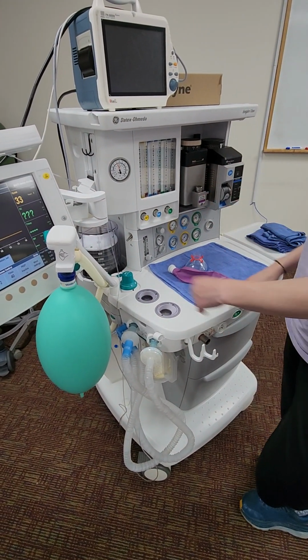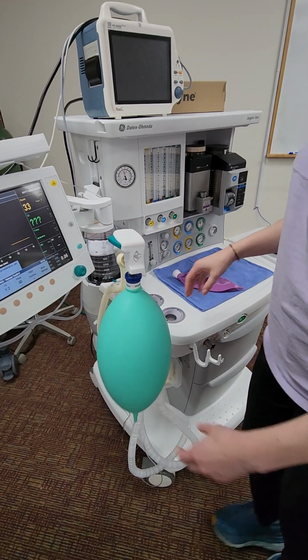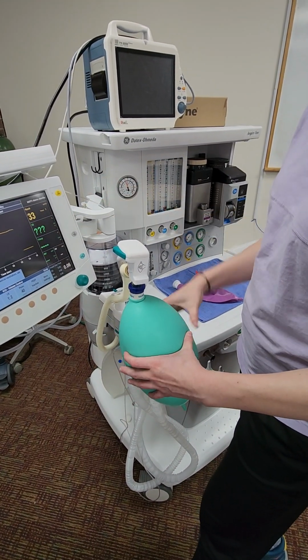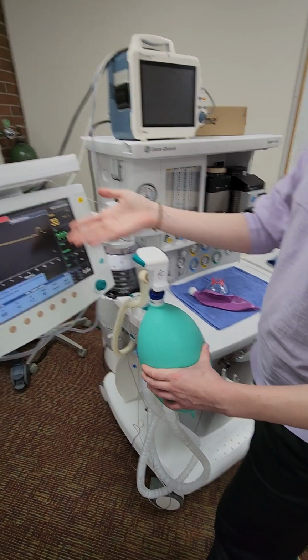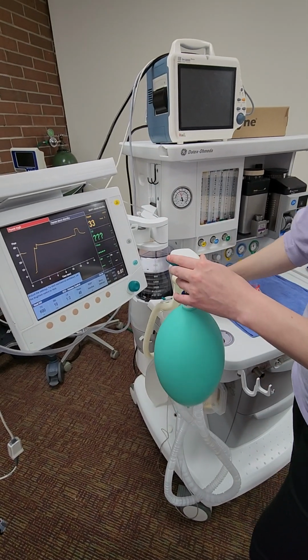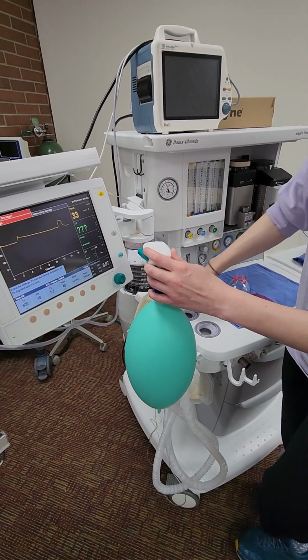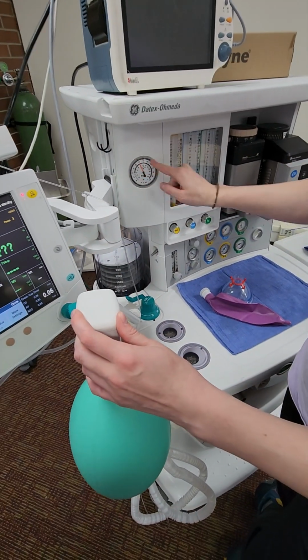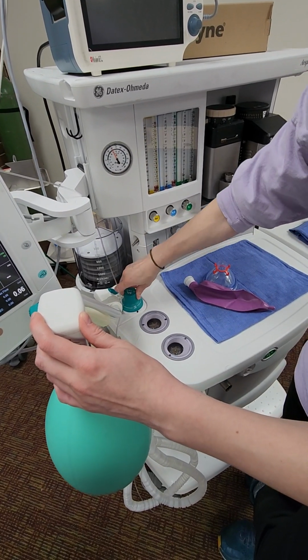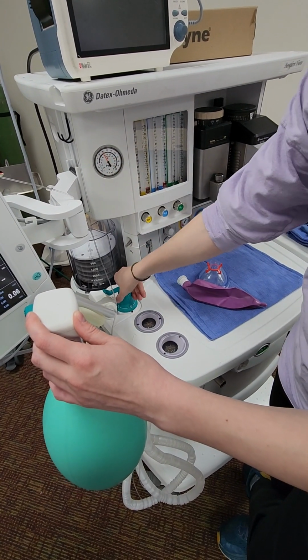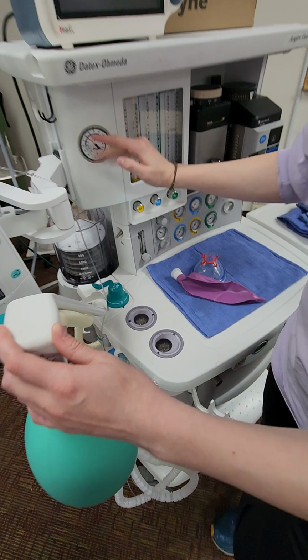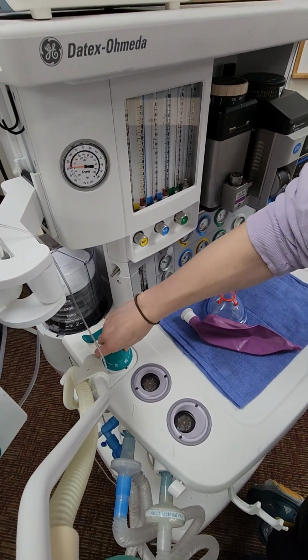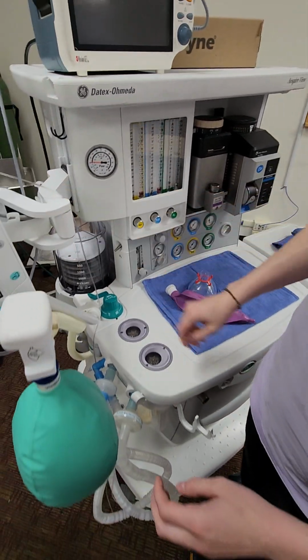So then after the 10 seconds, you can do this high pressure test on your monitor. So you squeeze it, it alarms, that's a good thing. So now you'll go back to your APL, you'll slowly start opening it and watch the valve fall too, so these should match. So we're at 30. That should still be at 30. We're at 20. This should fall and hold at 20. Now we're open. That should be a 0. So that's a good thing.